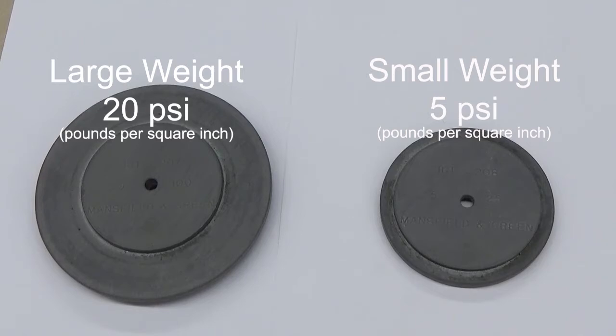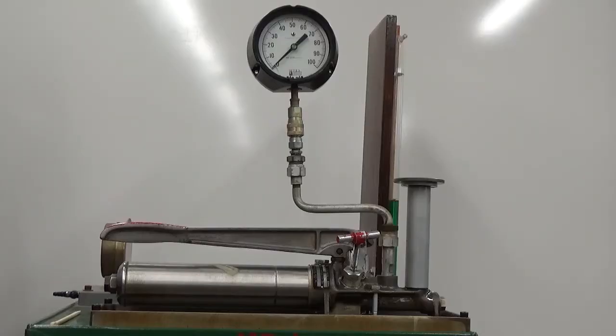The large weight is the equivalent of 20 psi, and the small weight is the equivalent of 5 psi. There are 4 of each of these weights, which allow us to calibrate in 5 psi increments a calibration curve from 0 to 100 psi. In this example, we will be calibrating the pressure gauge to the equivalent of 45 psi.